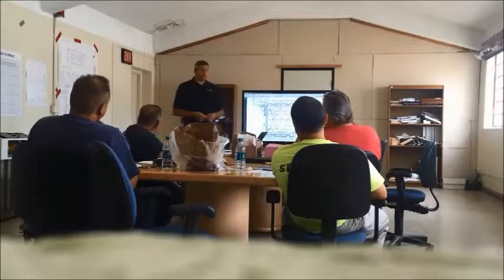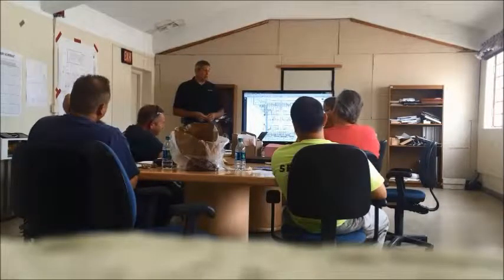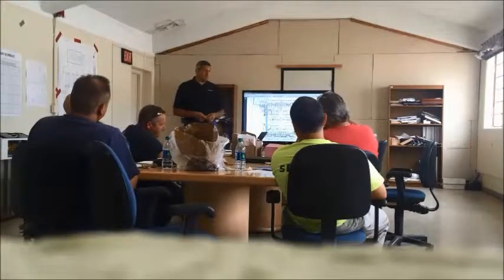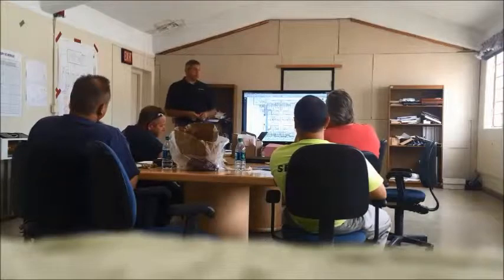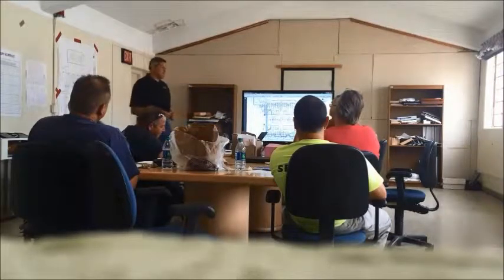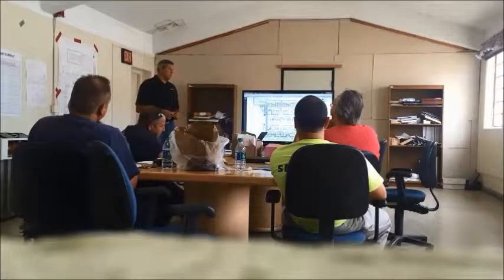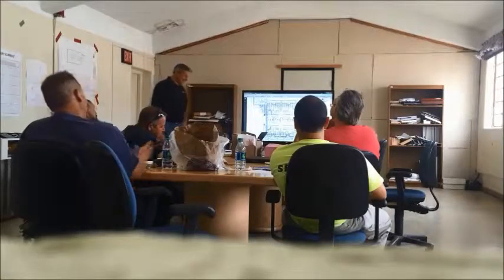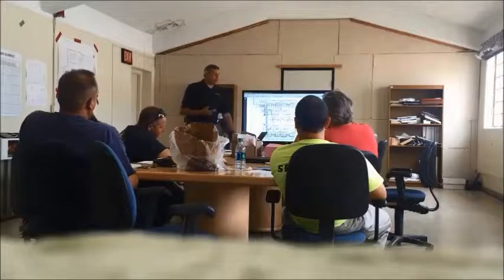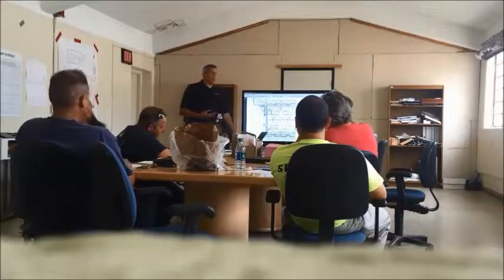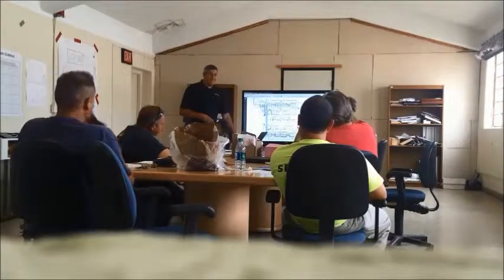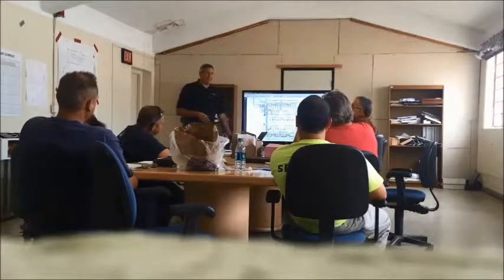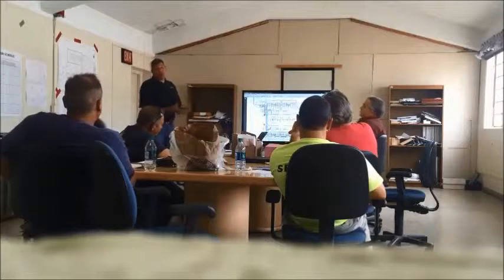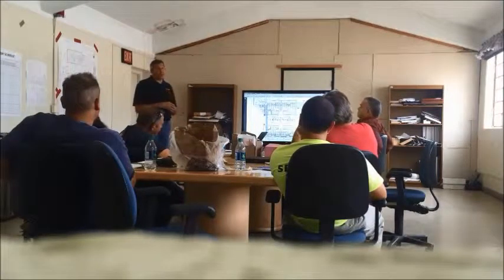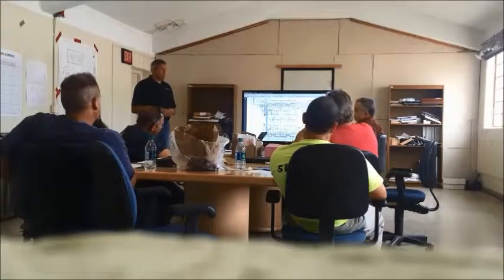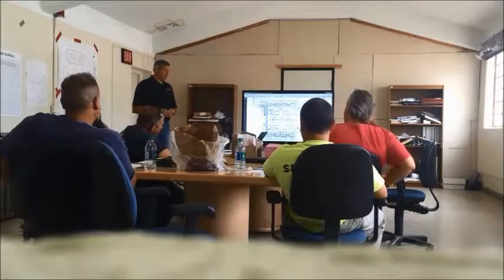So you're only monitoring dew point, but not doing anything with it right now, today. Yeah. And we do have the ability to adjust if we optimize in the future, taking that 58 slowly down or slowly up, depending on what we're trying to achieve. That's correct, and know that it will start raining at 46 degrees or whatever. You could start a more elaborate routine. You could say, if there's a demand request for cooling, don't allow the chill water to come within 2 degrees of dew point, or 1.5, or however you want to start fine tuning until you start getting drip throughout the building. But really, this whole building is driven off of chill beams. That's the primary means of cooling in this building. They're just constant chill beams, so it should be no touch, and let some of the other systems play catch-up.